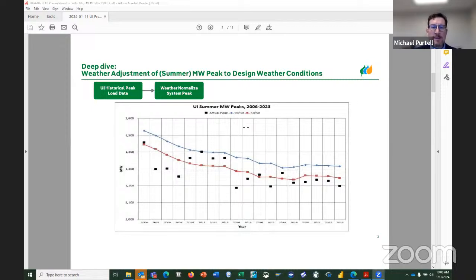The bluer line is our design condition for distribution planning. That's a weather condition that we would expect to occur once every 10 years. Again, stated another way, the probability of occurrence is 10% each summer. So we see that we've had one actual peak in the last 16, 17 years that has hit that weather condition. So that again passes that smell test, if you will.